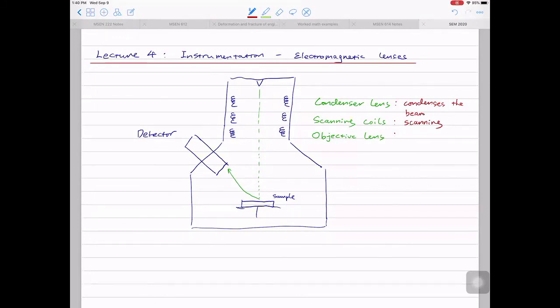Moving to the objective lens: the purpose of having an objective lens is to focus — the aim is to focus the image. On an SEM, you have a knob called 'focus' on FEI or Zeiss instruments, or called 'working distance' on the TESCAN instrument. When you put the sample in, in most cases the image is blurry. Then you turn the focus knob to bring the image into focus. What you are actually doing is changing the strength of the objective lens to bring the image into focus.